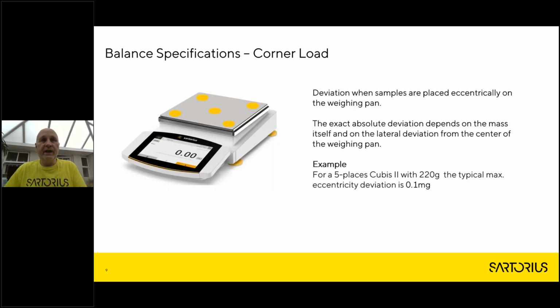The third specification we're going to look at is corner load error. Corner load is exactly what it says. If you don't place your sample and your tare vessel in the center of the balance, you will be incorporating an error. This error we call eccentricity or corner load error. Now we actually test this error on balances by placing a weight in the center of the pan, zeroing the balance, and then placing it systematically at the 4 different corners of the pan to actually find out how much linear error is on that particular balance.